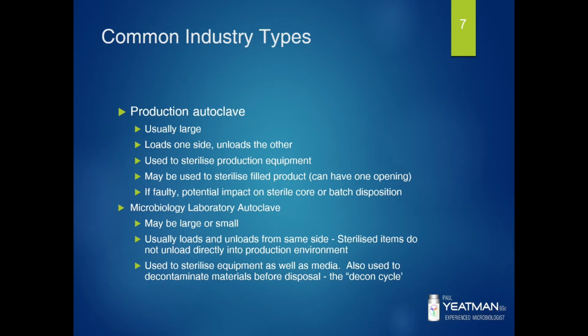If faulty, this has a potential impact on the sterile core if it's sanitising things into the room, or could affect batch disposition if it's a terminally sterilised function. For the microbiology autoclave, they may be large or small, all depending on your needs and what your URS, which hopefully was written before you got the unit, specifies as your needs and wants. These autoclaves usually load and unload from the same side. Sterilised items do not unload directly into a production environment. They might unload into your sterile testing suite, as discussed. They are used to sterilise equipment as well as media, and also to decontaminate materials before disposal using what's generically called a decon cycle.